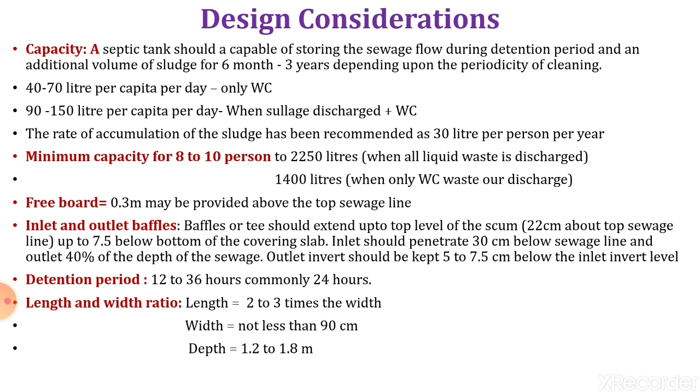Inlet should penetrate 30 centimeter below the sewage line and outlet 40% of the depth of the sewage. Outlet invert should be kept 5 to 7.5 cm below the inlet invert level. Detention period of 12 to 36 hours, of which the commonly adopted figure is 24 hours.